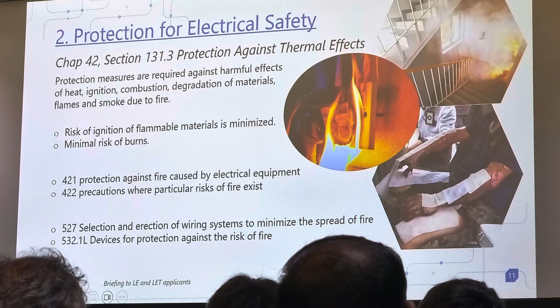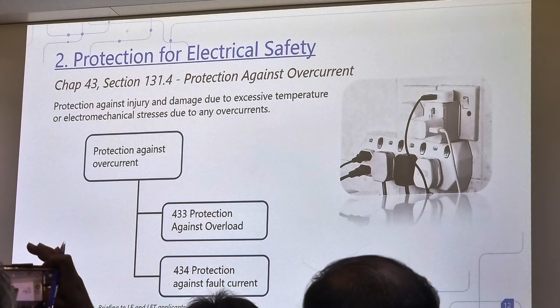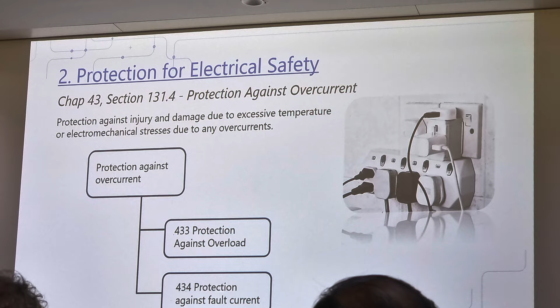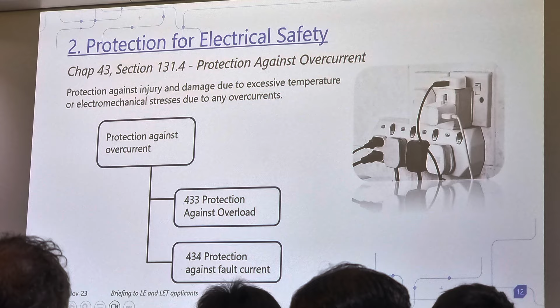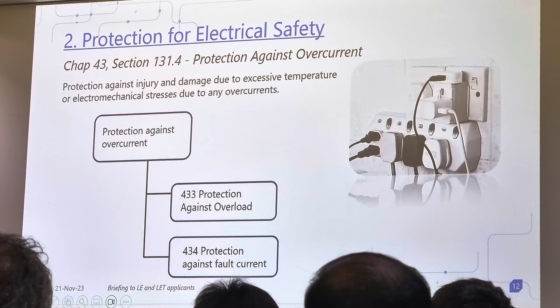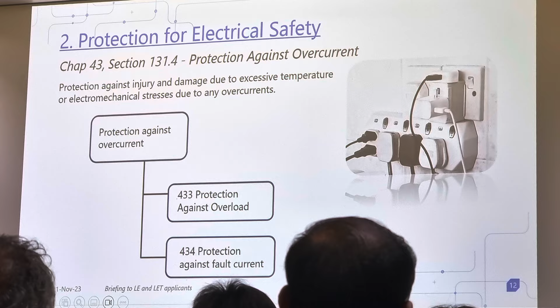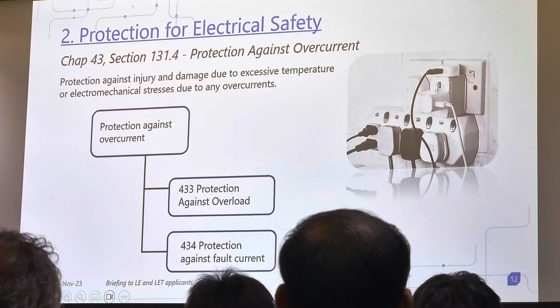Now, the next one will be protection against current, electric shock, and thermal effects. The next one is overcurrent protection. I think this one most of us are very familiar with. Overcurrent can be overload, can also be a fault. Overload means that the circuit is healthy, nothing wrong with the circuit. It's just overloaded. You plug too many equipment onto the circuit, it's overloaded. You put too many things on the machine, overloaded. But once you remove all these loads, it's okay, it's back to normal. So under overload protection, it's still a healthy circuit. You don't need to repair the circuit, you don't need to do anything about the circuit. So you need to remove the overloaded equipment.